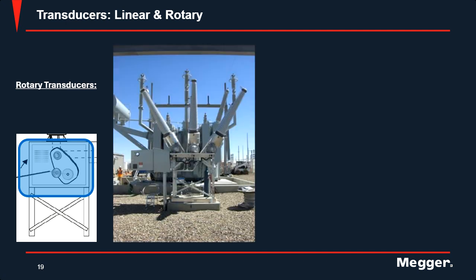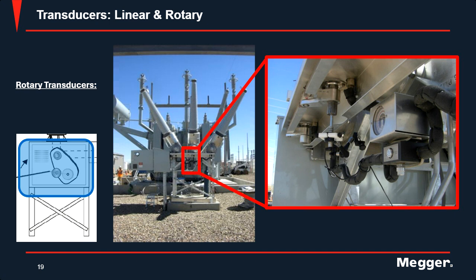Then we have a rotary type. So the rotary type outputs a value in angle, typically in degrees. This is where those conversion tables may come into play. This depends on the manufacturer, if they gave it to you in both linear or in degrees. The linear type outputs a value in length, typically meters or inches. And as I said, the conversion tables are generally needed for the rotary style.